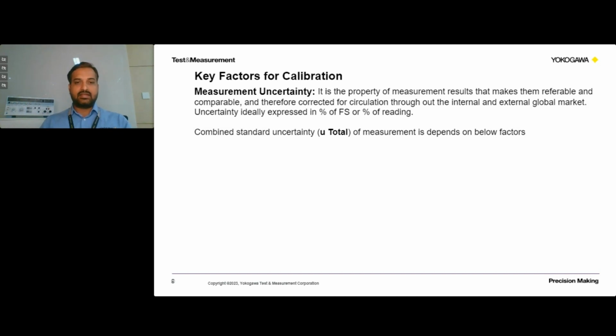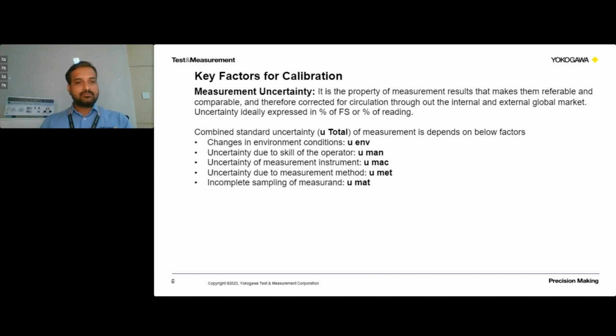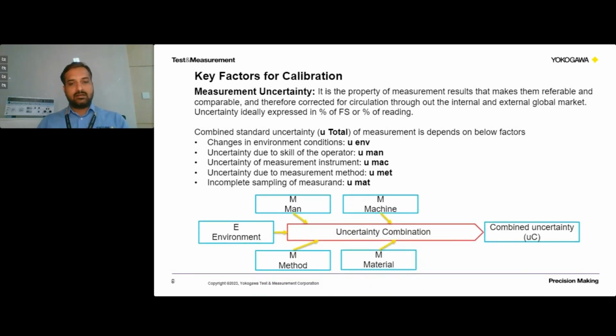It will be affected by a set of factors when we do the measurement. Those factors are uncertainty due to environmental conditions such as temperature and humidity, and uncertainty due to the skill of the operator, if any error is added because of unskilled manpower or mistakes from the operator. And uncertainty because of the measurement instrument. By default the instrument will have certain uncertainty because of voltage fluctuations or the semiconductors involved in the instrument. And uncertainty due to measurement method: what method we are following for doing the testing also adds to the uncertainty. And incomplete sampling of the measurement, that means improper measurement of the parameter, also adds to the uncertainty. So overall these factors will give us the combined uncertainty.